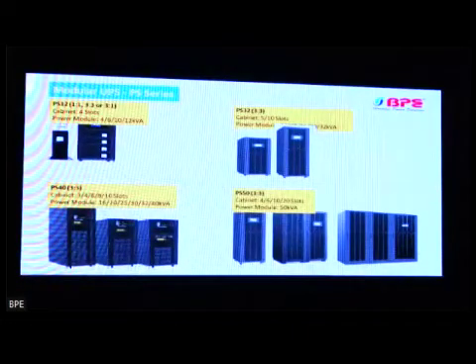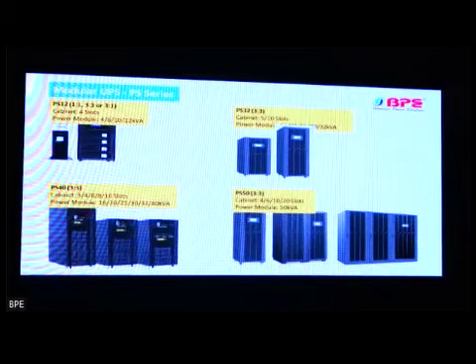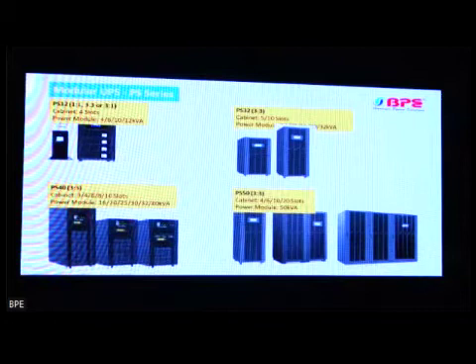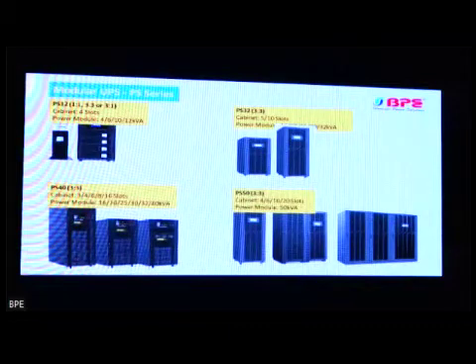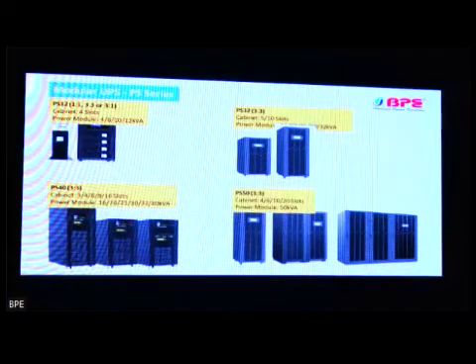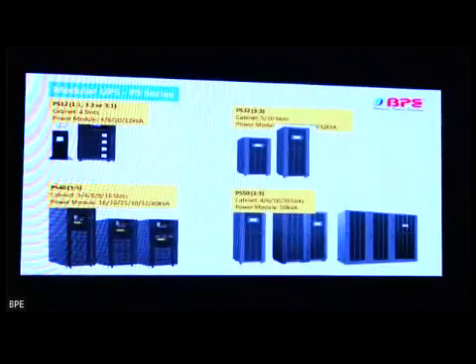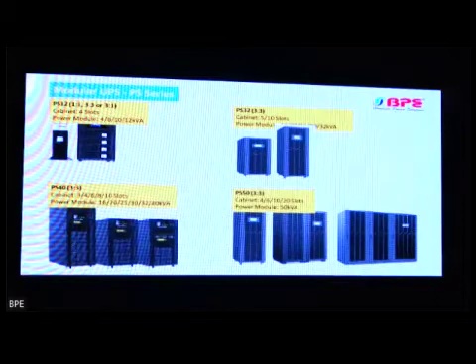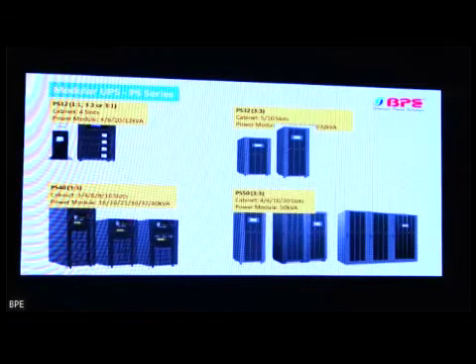Now we have modular UPSs suitable for data centers and other IT applications. Basically, we have 4 kinds of modular UPSs in the PS series: PS12, PS32, PS40, and PS50. The PS12 series has an individual LCD on each module. Basically, the module is a UPS, and you can use every module as a standalone UPS also, because it has an rectifier and inverter inside. And we have a 7-inch LCD on the frame also. And this is the USP of BPE. No other competition has this kind of modules with inbuilt LCDs.